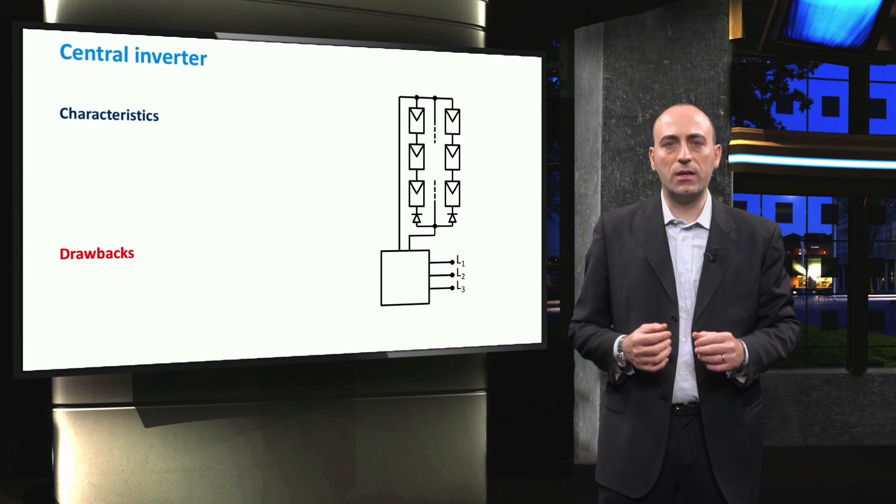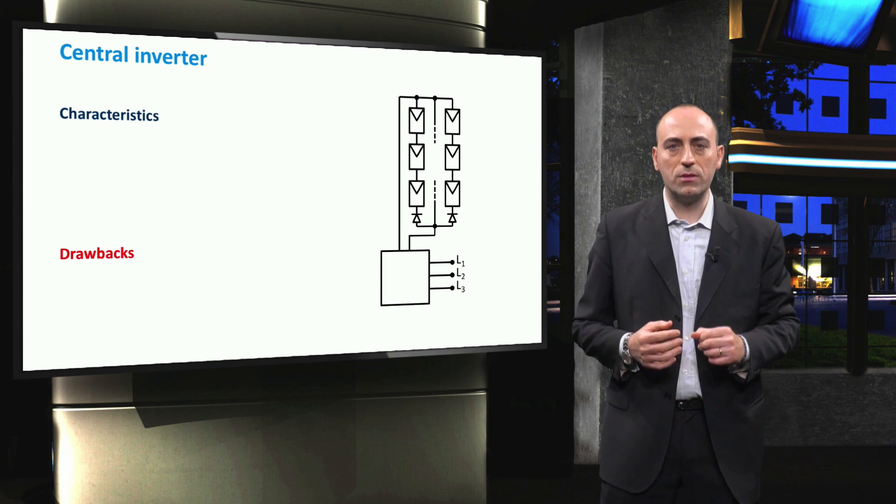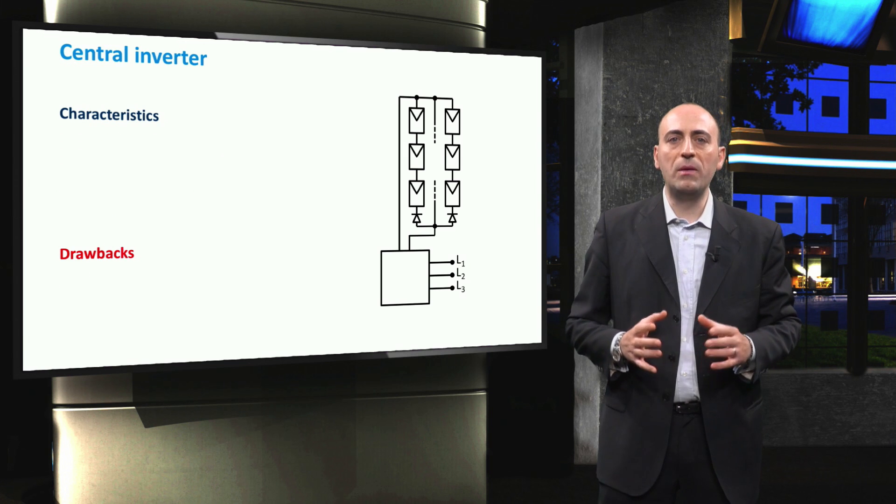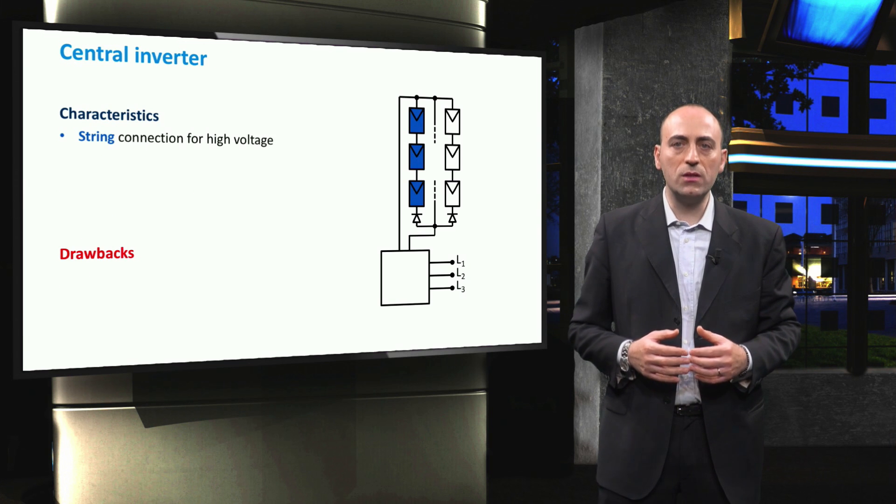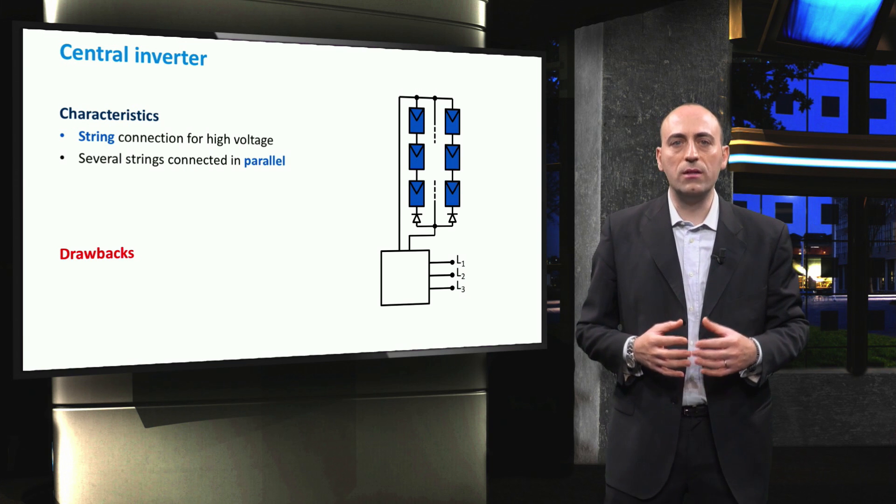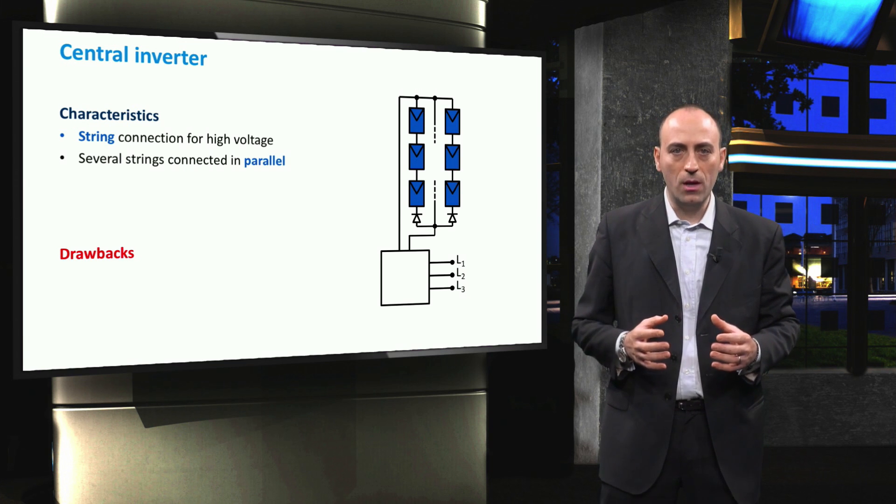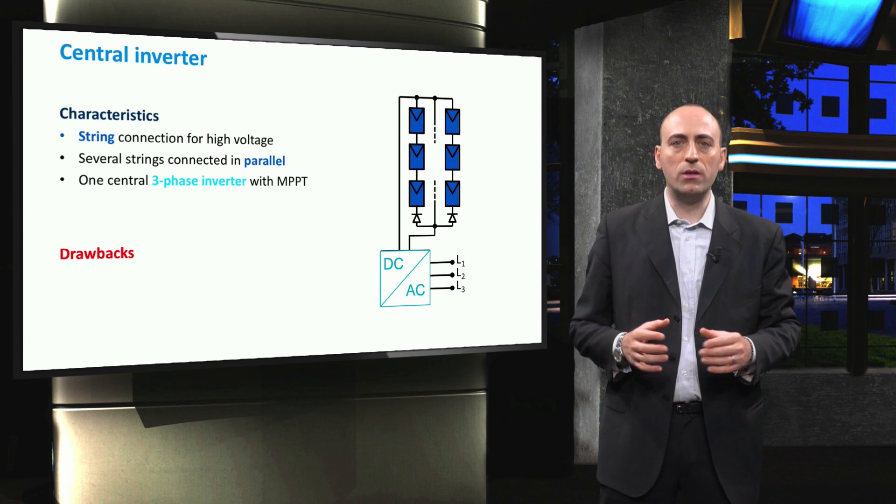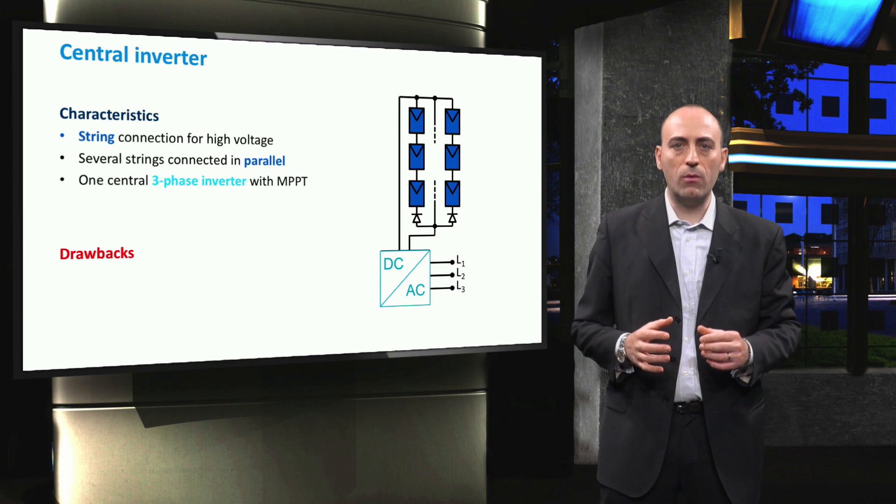Let's start with the simplest architecture employed in PV systems, the central inverters installation. Here we have that PV modules are connected in strings, leading to an increased system voltage, and then the strings are connected in parallel, forming a PV array, which is connected to one central inverter.